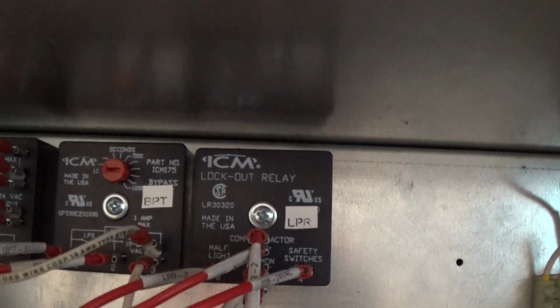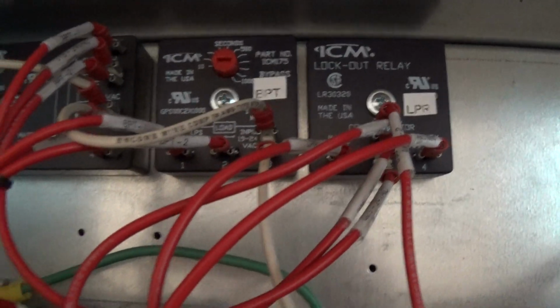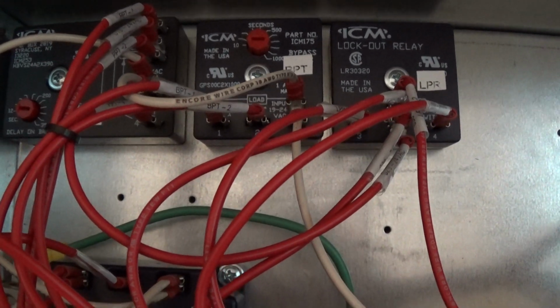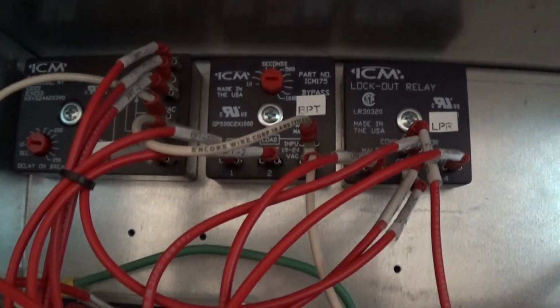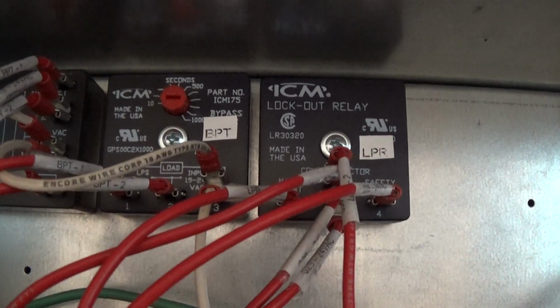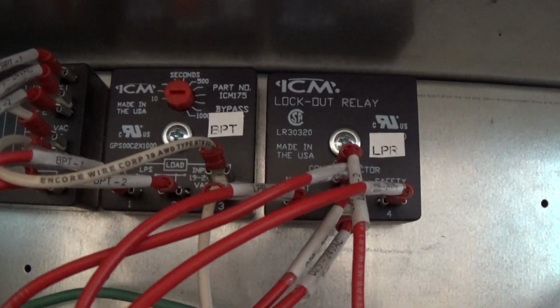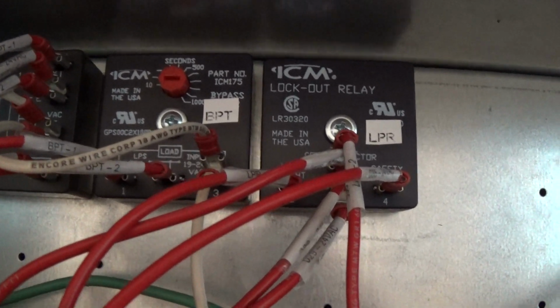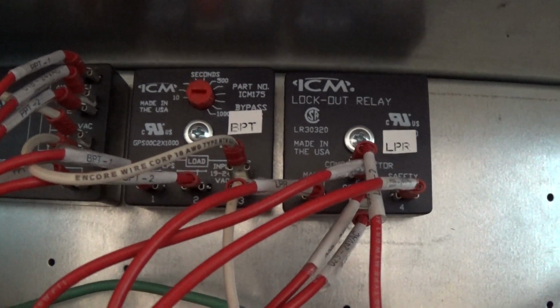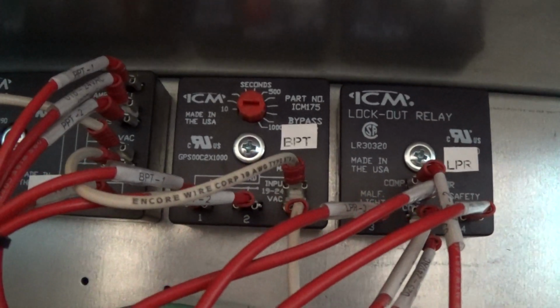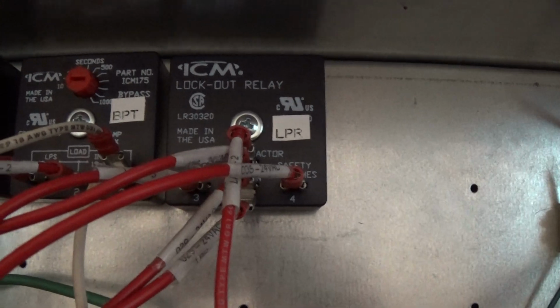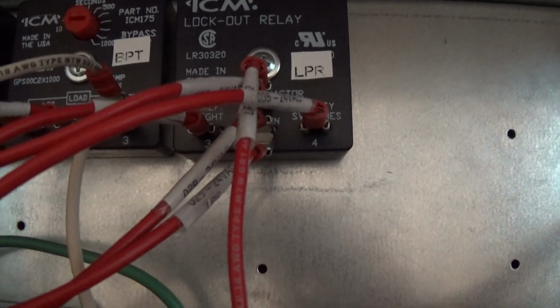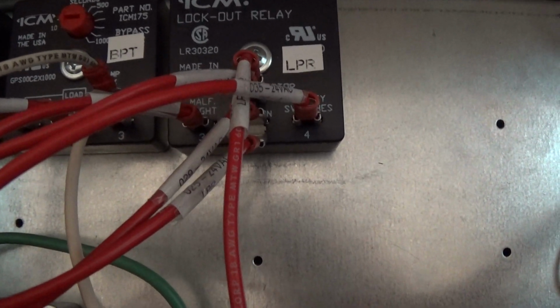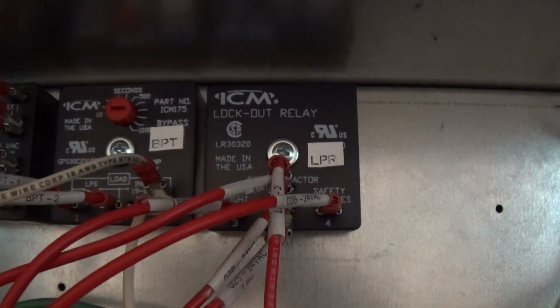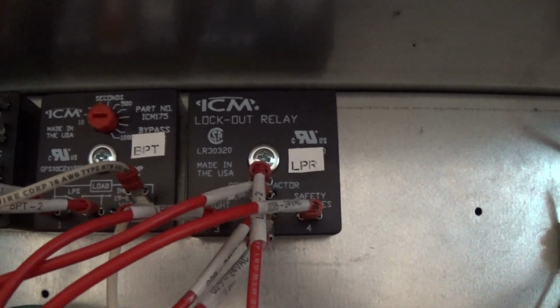Next to that is the BPT timer. That's in the middle. That's our bypass timer. That's basically a low pressure bypass timer, so upon initial startup you won't get a nuisance low pressure alarm, which sometimes can happen the way chillers operate. So that's an extra feature we have there. The LPR is simply the lockout protection relay. That will lock out the compressor in the case of a serious fault or unsafe condition.